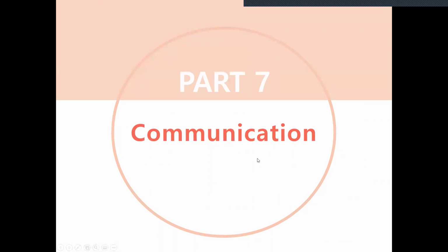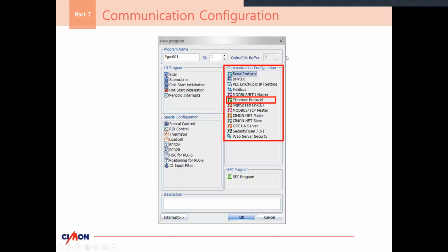Okay, so for part 7 communication, this is asked a little bit, do we cover field bus? And yes, we do, but the field bus is not embedded internally for the PLCS. That is something you would have to get another module for, or you would have to talk through the HMI. And I recommend talking through the HMI because it has so many protocols in general to talk with that we'll cover those tomorrow, but it's just a lot cleaner when you talk through the HMI.